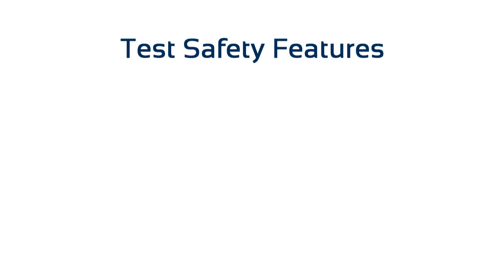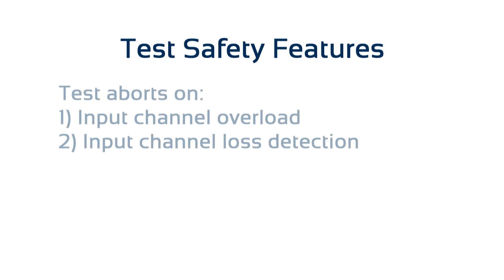Crystal Instruments vibration controllers are designed with many different safety features. The system detects when input channels are overloaded or lost, which can indicate a sensor fault or disconnect. The test will abort if this occurs.